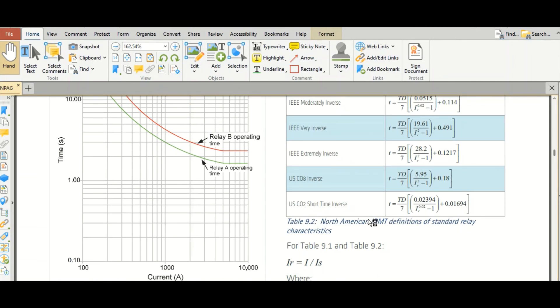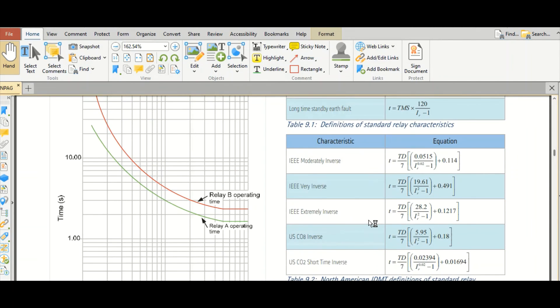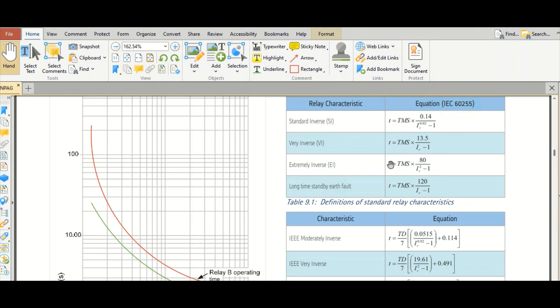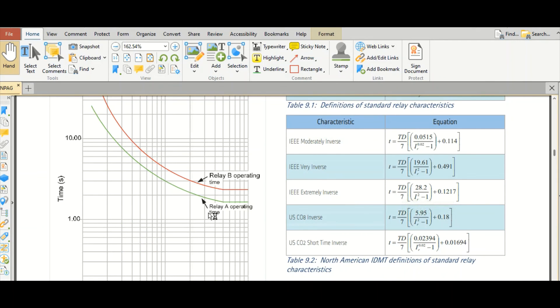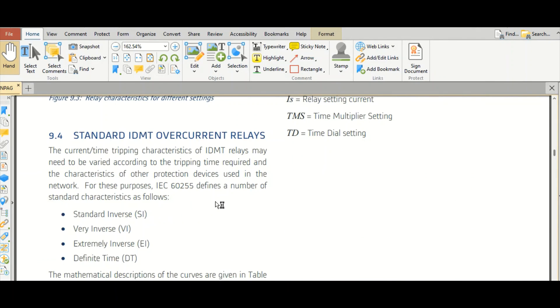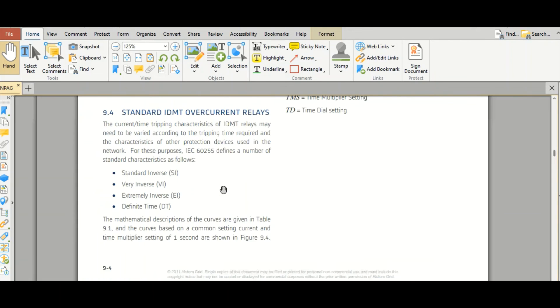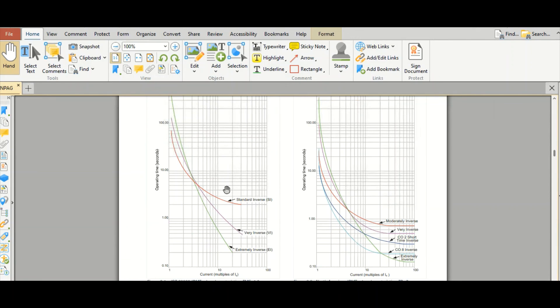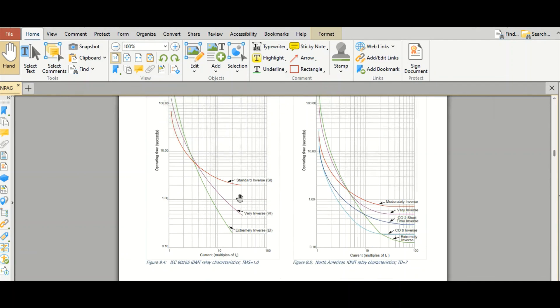So based on this equation, the normal inverse curve will follow this equation. Very inverse curve will follow this equation. Extremely inverse curve will follow this equation. So based on these equations, the IDMT relay characteristic curve will be generated like this. This can be set or modified as per the requirement of device protection coordination settings.